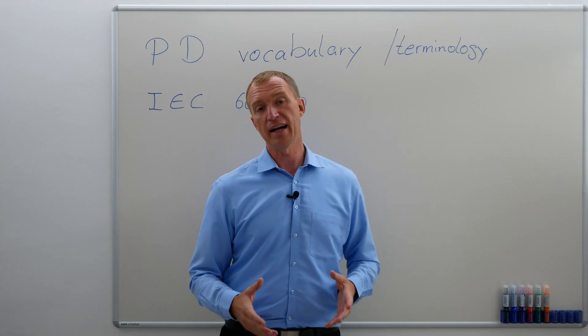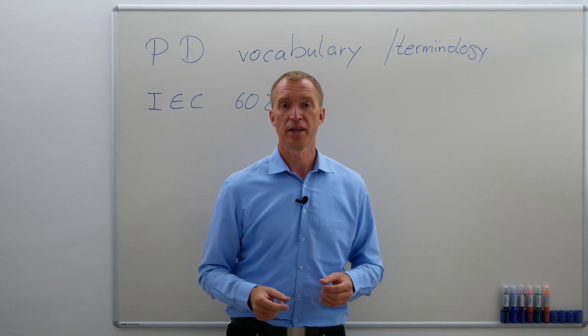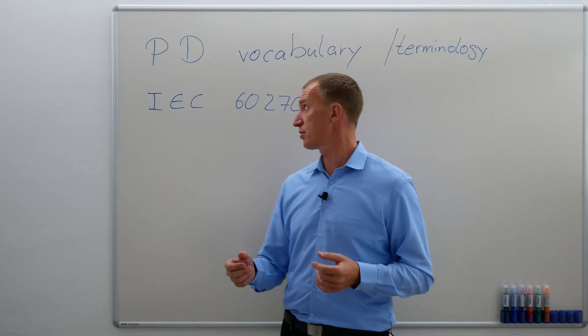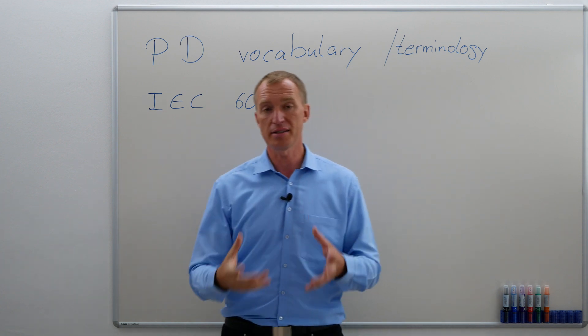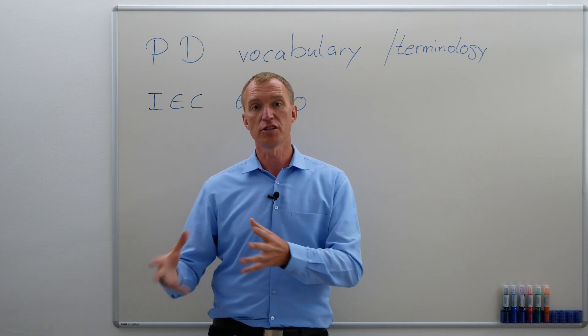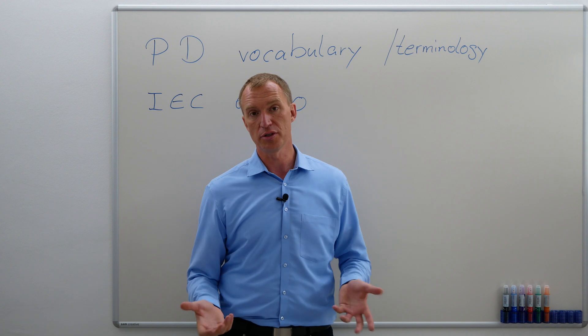We also have the IEC, and here as well is a short list of some of the standards — it's not complete. There are standards about testing partial discharges on cables, on rotating machines, on transformers. The majority of these standards actually refer to the IEC 60270, which is a standard that only deals with partial discharge testing and defines a lot of the vocabulary we are using.